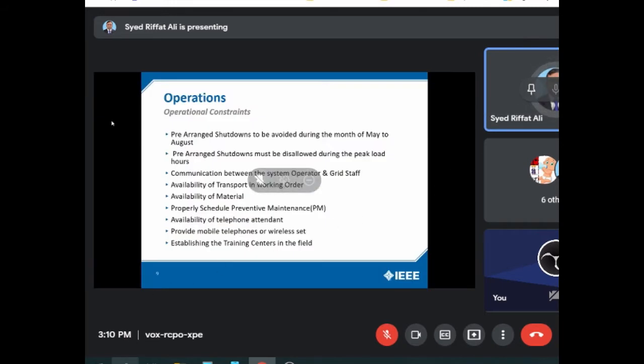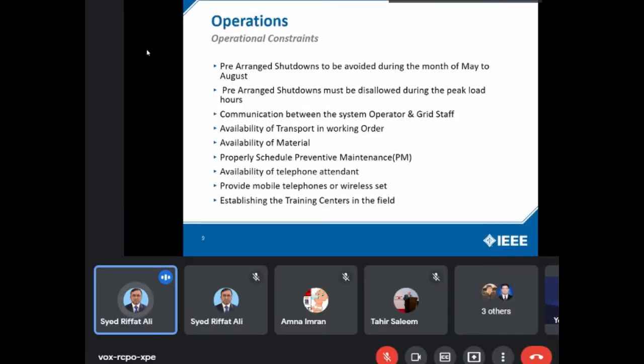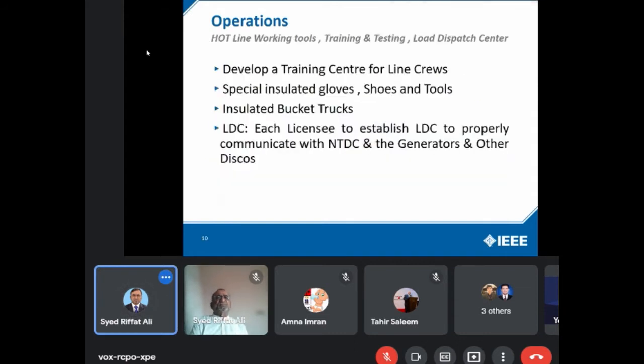Then communication between the system operator and the grid operator, availability of transport in working order, availability of material, properly scheduled preventive maintenance, availability of telephone attendants. Of course, technology has greatly affected this phenomenon as well. We have social media at the grid and system operators level as well. And the establishment of a training center in the field. Of course, this is not practiced in Pakistan, but hotline working tools, training, testing, and load dispatch guidelines are also provided for hot working as well. So, although this is in very broad terms, a separate SOP is required for handling these hotline working tools as well.